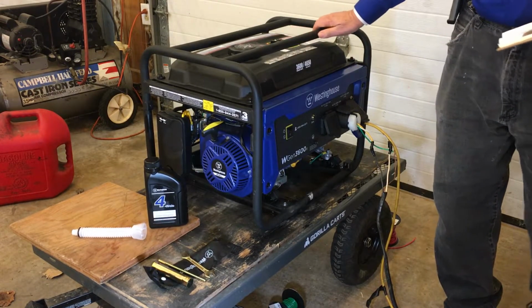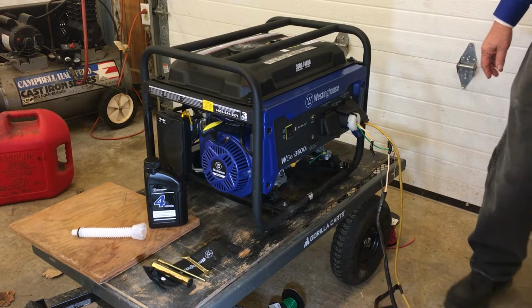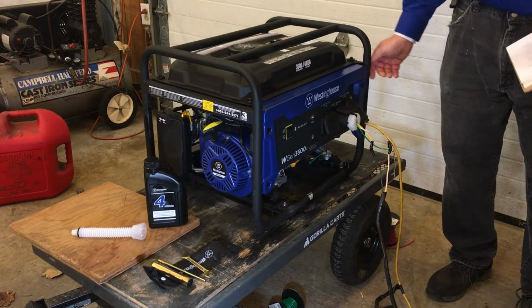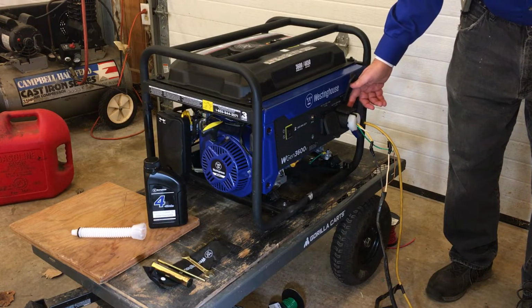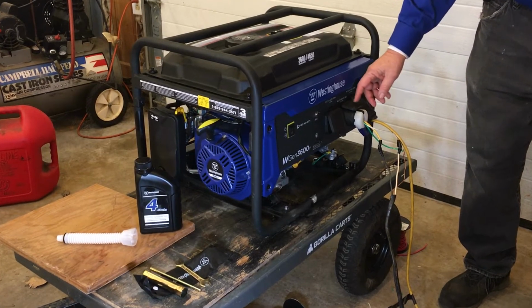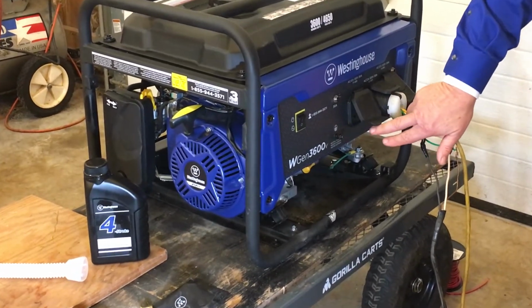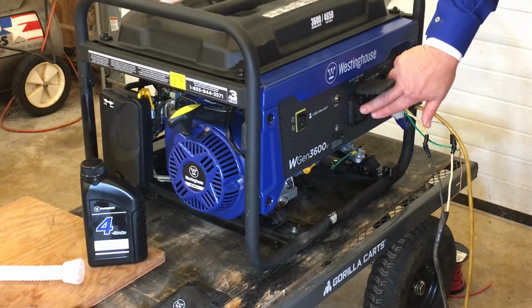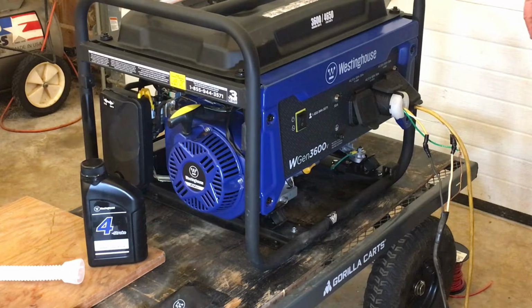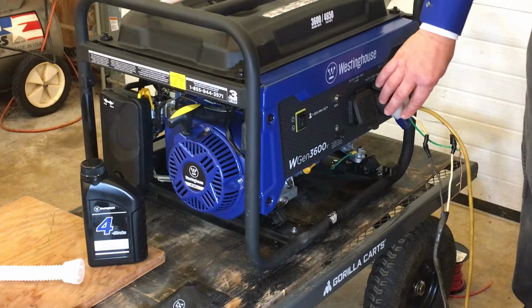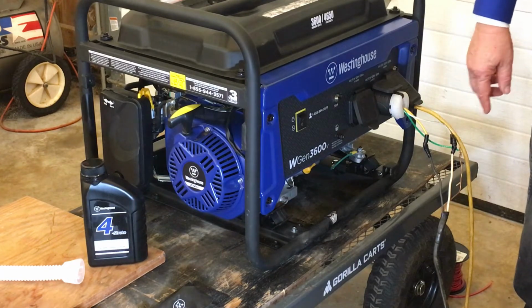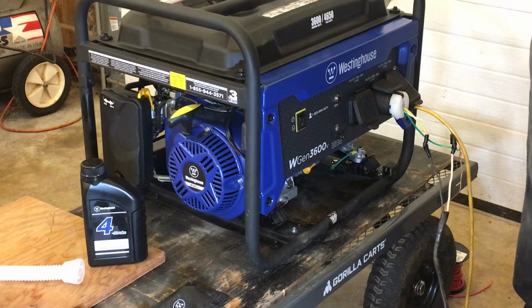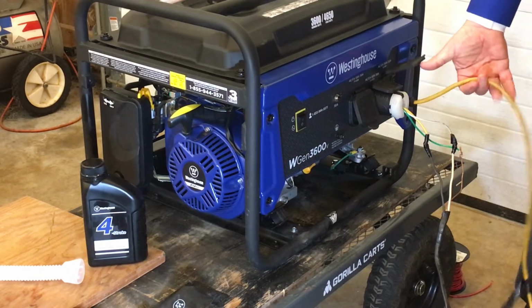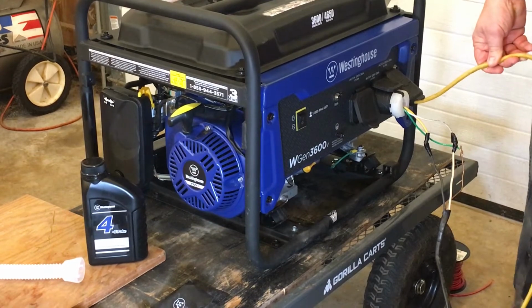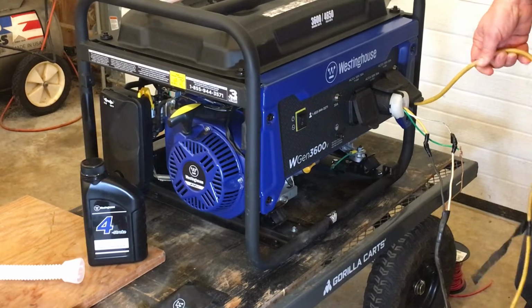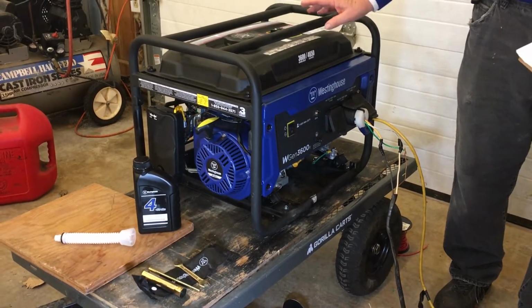This generator is rated for 120 volt output and is equipped with an AVR, automatic voltage regulator. It has a standard two outlet, a duplex outlet here. It also has a twist lock and a third outlet, 30R, I believe it's a 30 amp rated outlet for going into an RV or something like that. At the present time, I've got a twist lock jury rigged in here. The cable coming out is a number 10 cable going to my load bank, which we'll be looking at in a few minutes. And also there is an extension cord plugged into this receptacle that's going to a Kill A Watt unit, which will give us just an indication of the frequency that this unit is running at.